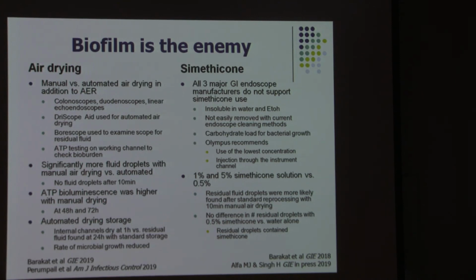And then they used the borescopes to look inside to confirm that there was no residual fluid, as well as ATP testing on the working channel. And they had significantly more fluid droplets with the manual air drying, and with automated, there were no fluid droplets after 10 minutes.